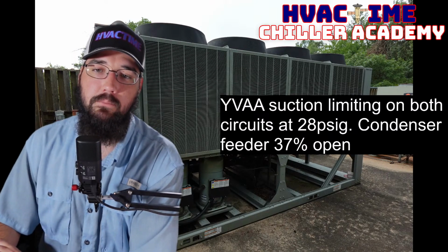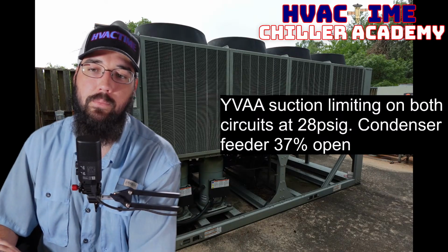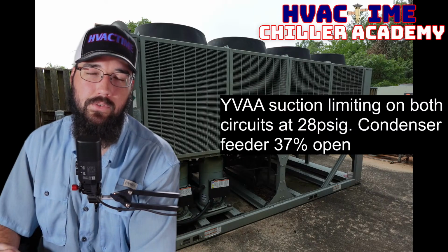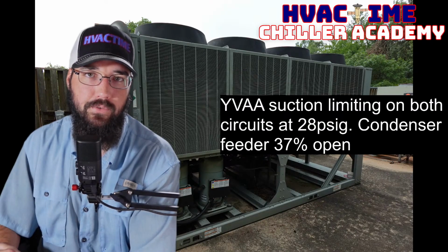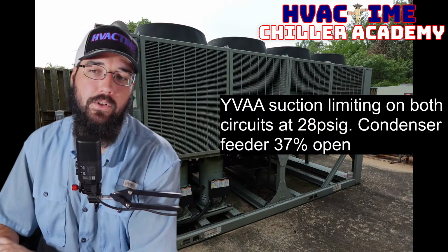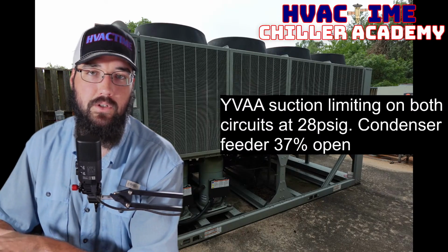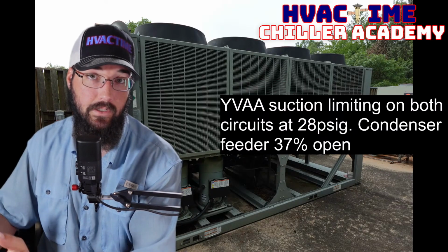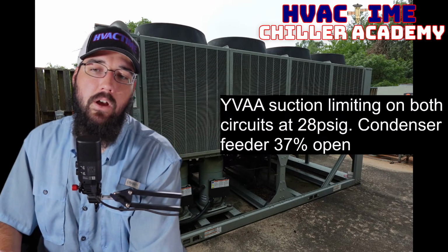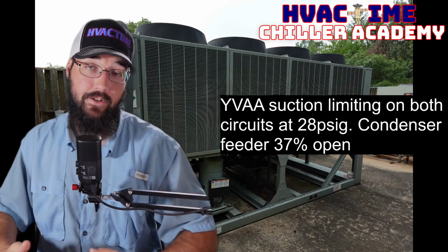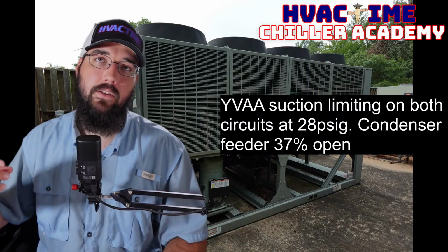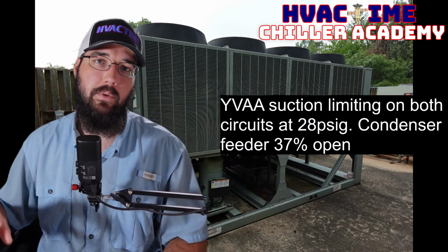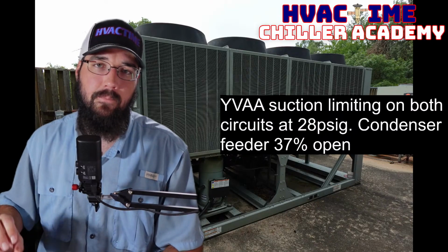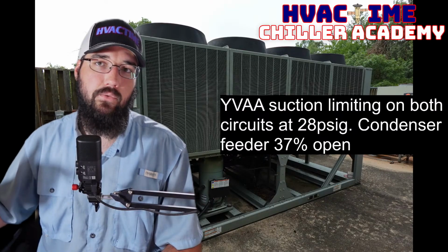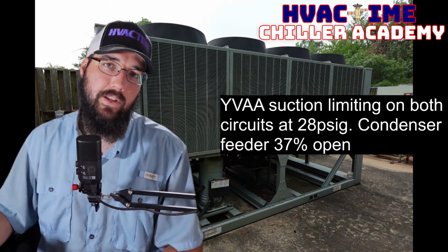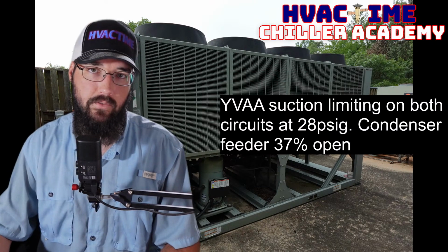So YVAA suction limiting on both circuits at 28 psig, condenser feeder 37% open. My thoughts on that: because it is both circuits, and if you had a low charge, for example, both circuits rarely leak at the exact same rate. These are independent circuits; they share the same evaporator, but everything else is completely independent. So being that they're both operating identically, I would say it's probably not a refrigerant issue, because with the YVAA, the feed valve is opening and closing based off of subcooling off of the condenser. So technically, if you start to have a low charge scenario, the feed valve will limit how much it's feeding off of the condenser to keep subcooling up, which will starve the evaporator. That's my understanding so far.